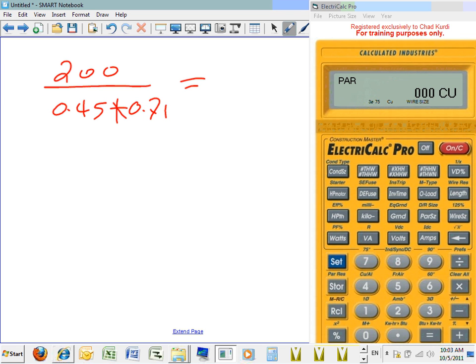Yeah. What? Did you guys find 0.71 from 310.15(B)(2)(a)? 0.45 is coming from the bundling, table 310.15(B)(3)(a). Can you guys see for 21 to 30, the derating factor is 0.45, right? Okay, cool. So let's go divide these.